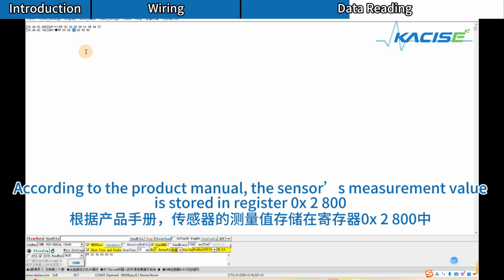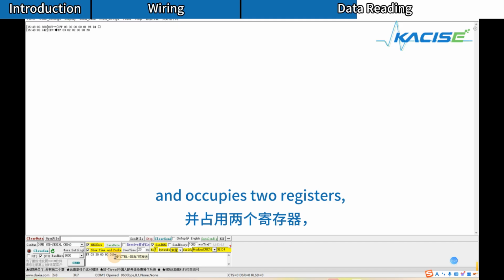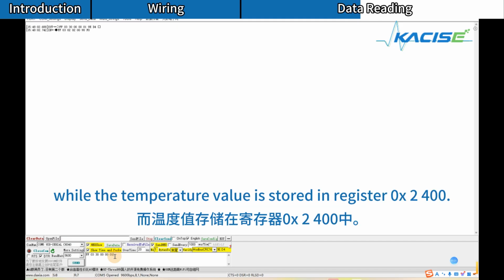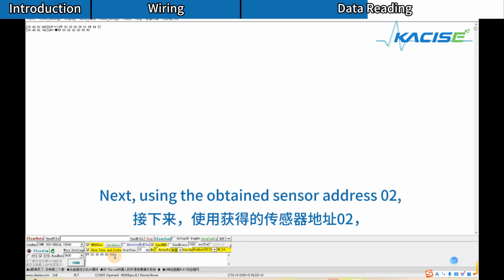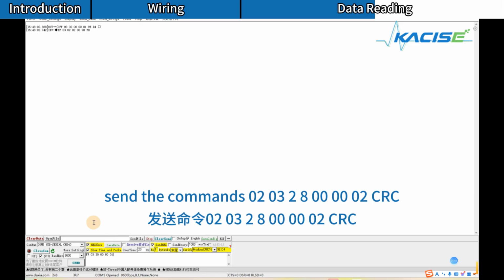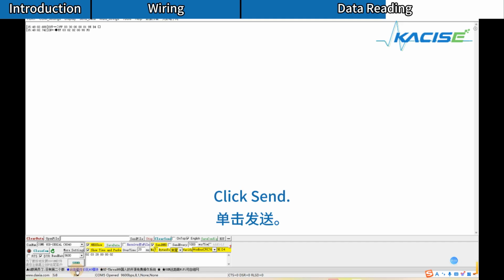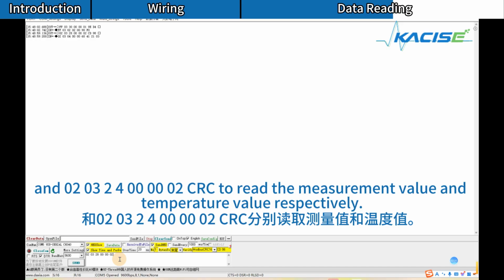According to the product manual, the sensor's measurement value is stored in register 0x2800 and occupies 2 registers, while the temperature value is stored in register 0x2400. Next, using the obtained sensor address 02. Send the command 020328000002 CRC. Click Send. And 020324000002 CRC to read the measurement value and temperature value respectively.